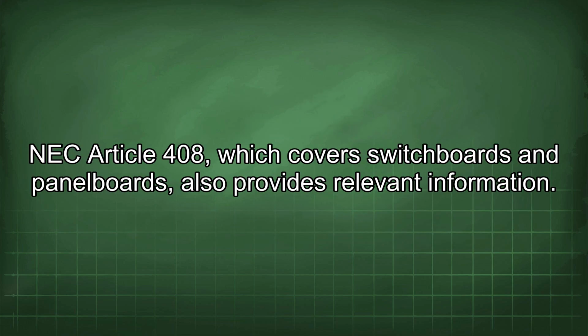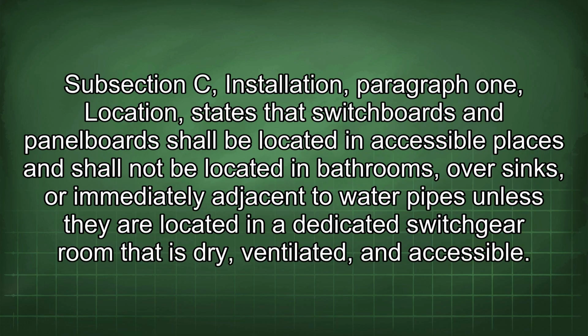NEC Article 408, which covers switchboards and panel boards, also provides relevant information. Subsection C, Installation, paragraph 1, Location, states that switchboards and panel boards shall be located in accessible places and shall not be located in bathrooms, over sinks, or immediately adjacent to water pipes unless they are located in a dedicated switchgear room that is dry, ventilated, and accessible.